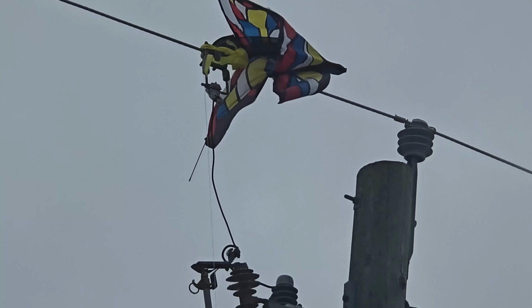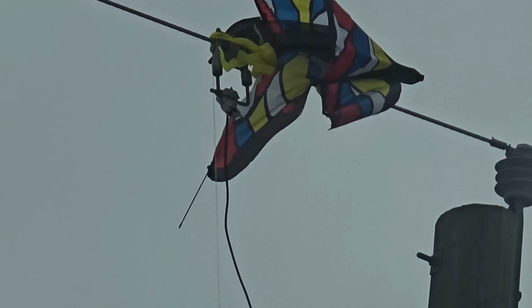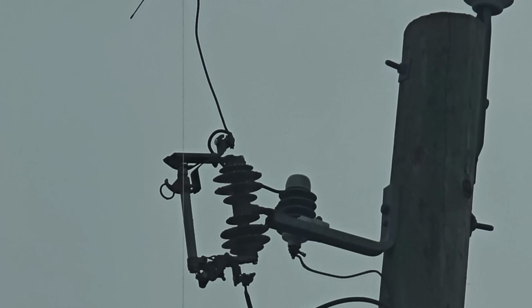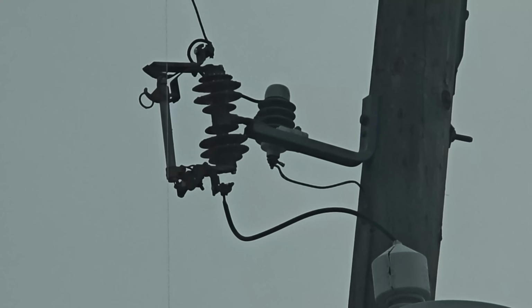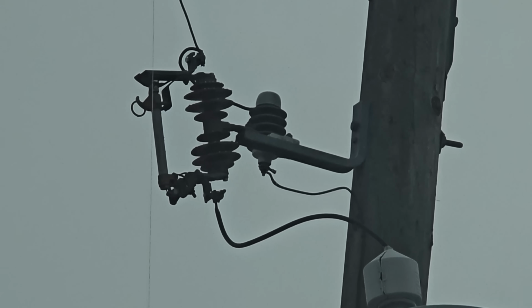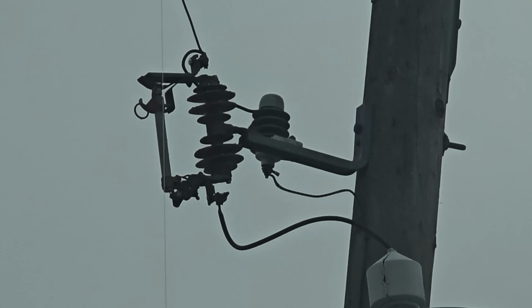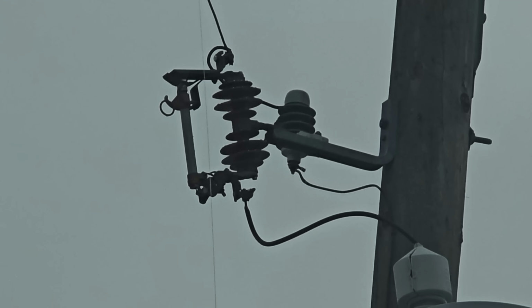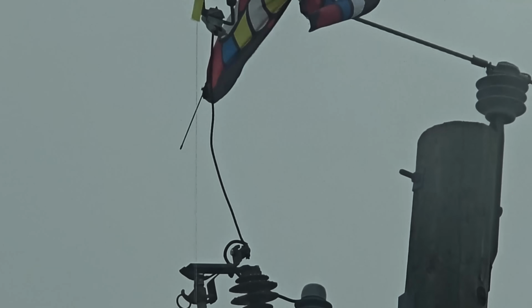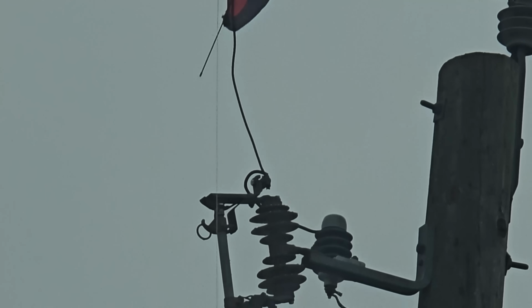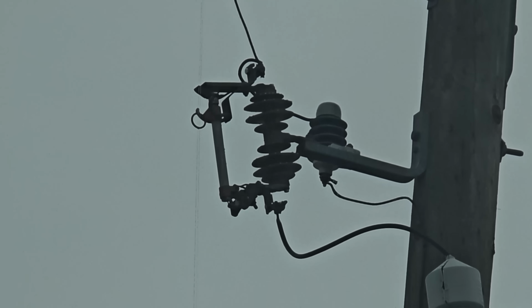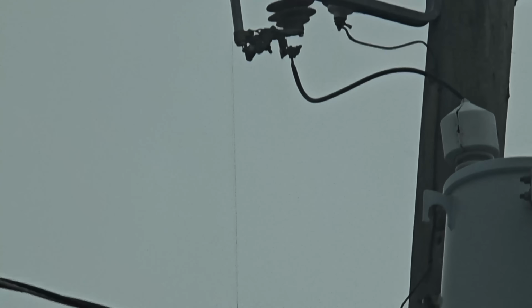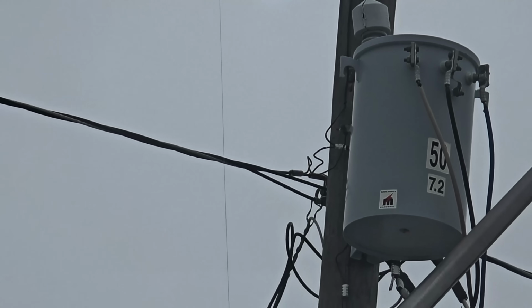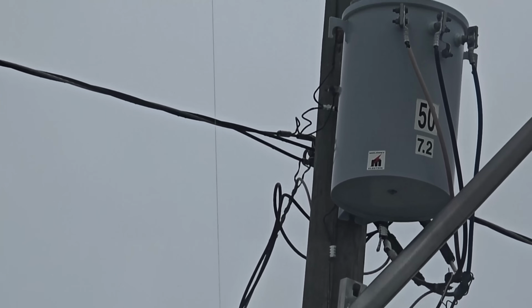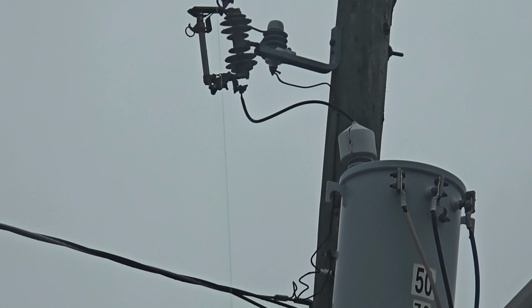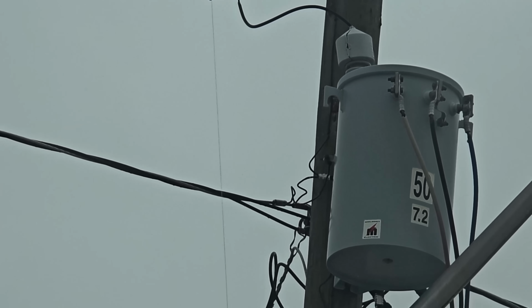Now what concerns me, you see that string coming off the kite, coming down past the cutout. That lightning arrestor on the right, bottom side of that's ground, is 0 volt, it's tied to ground. That cutout's 7200 volts. That kite string, it's not overly conductive. I would consider it a semiconductor. It's not an insulator and it's not a conductive material, but that doesn't mean it couldn't short out. So it is concerning where it's close to that bracket going down by the neutral and the transformer.